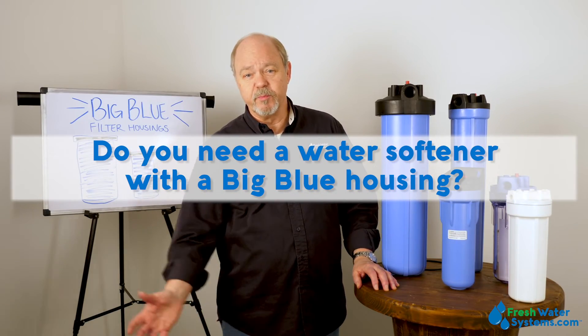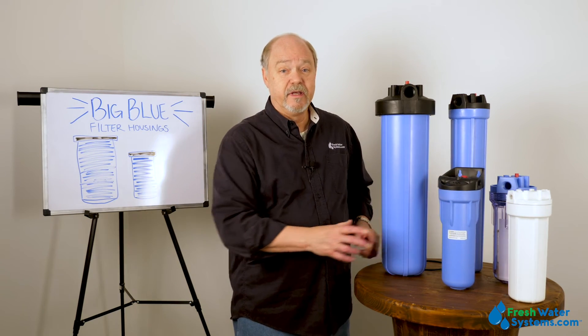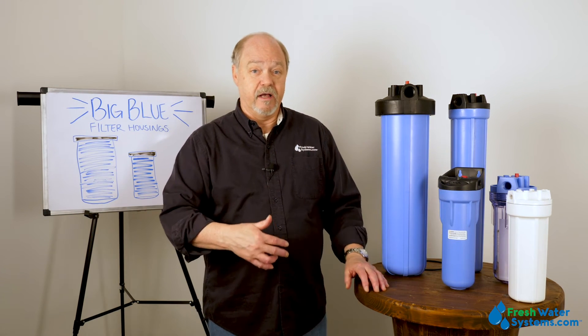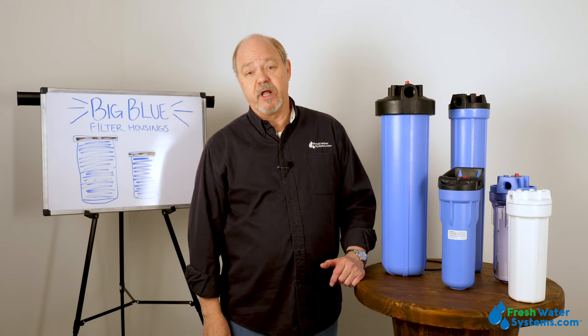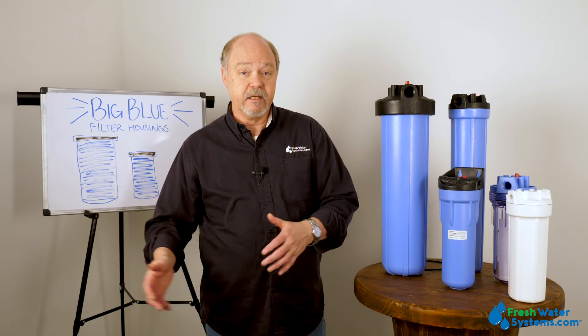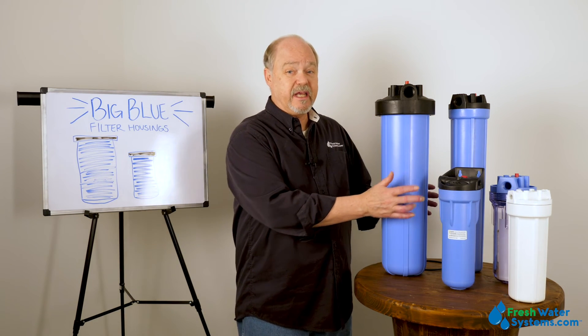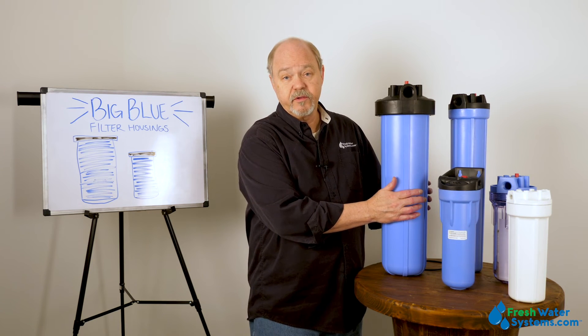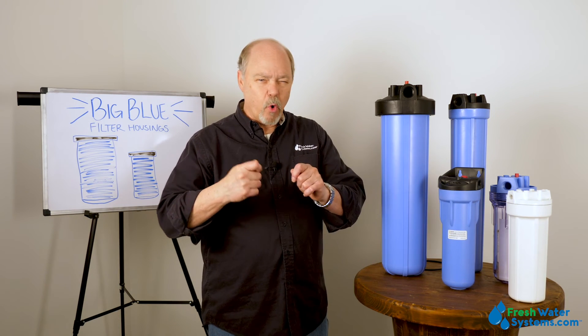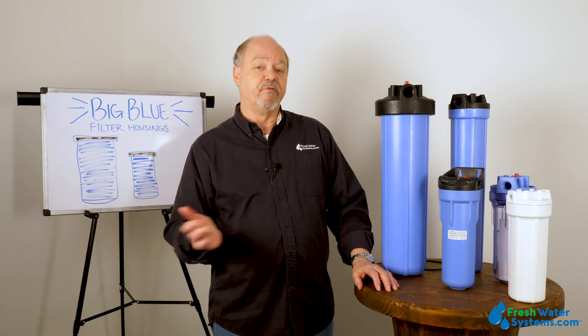Do you need a water softener with a big blue filter housing? Not always. Many times the big blue filter is pre-treating or protecting the water softener. For example, if we're working on a well water supply and we're having to get a lot of hardness out, but the well has a level of particulate in it, we'll hang one of these before the water goes into the water softener so it can capture the stuff the water softener can't deal with — sometimes oxidized iron, that's the stuff that makes the water change to an orange tint. We'll capture it with one of these types of filter housings before a water softener.